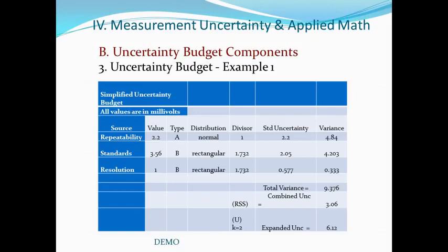Some uncertainty budgets also include the variance column as shown in the next column to the right. We said that variance is just the square of the standard deviation. Therefore, 2.2 squared is equal to 4.84 as the variance. We proceed on the following rows to do the same calculations. Look at the one labeled standards. This would most likely be taken off of a calibration certificate for the standard that is being used. The value shown here is 3.56.